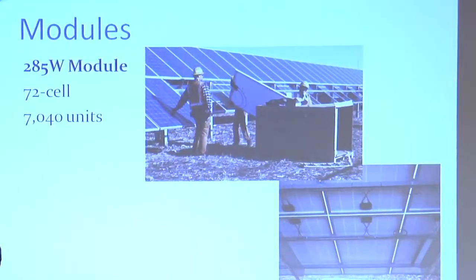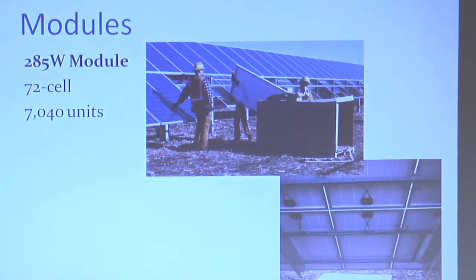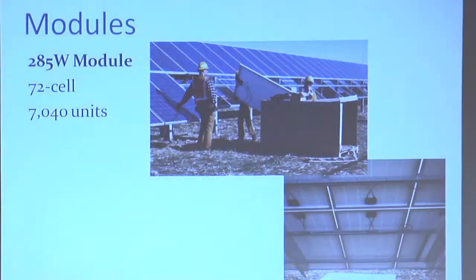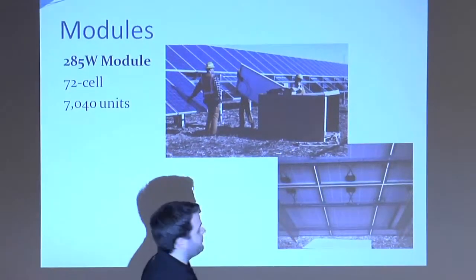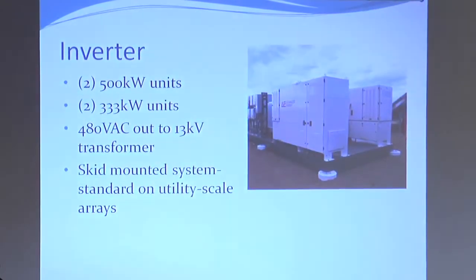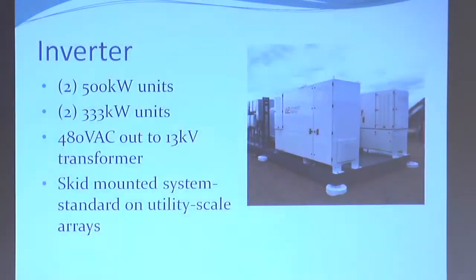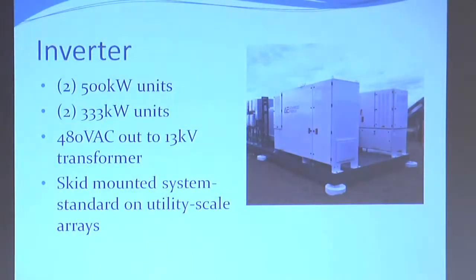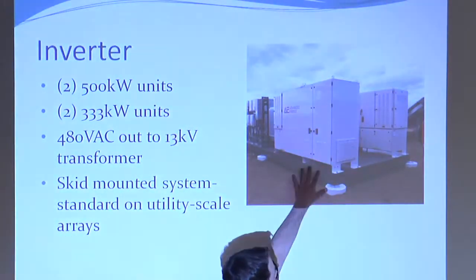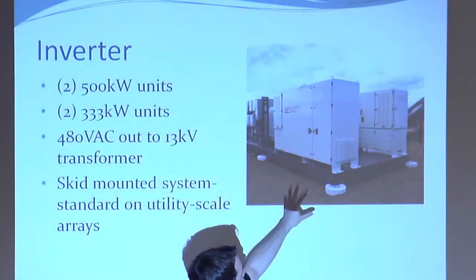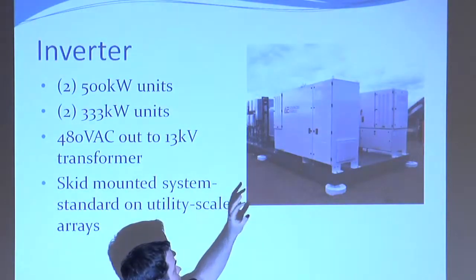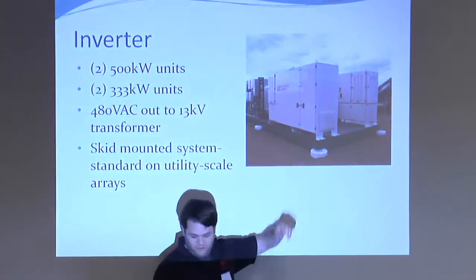4th. So the modules we used were 285 watt modules. That's a 72 cell module, so a larger format. There's 7,040 units. These are oriented in portrait, so they're just stacked one on top of one another. Like I said, we have 4 inverters out there, 2 500 kilowatt units and 2 333 kilowatt units. They put out 480 VAC straight to the transformer, which steps it up to 13 kV for interconnection to Xcel Energy. This whole system is mounted on a skid. It's got piers driven into the ground, and this skid holds the 4 inverters, the transformers, a couple switchboards, and all of the monitoring equipment as well.